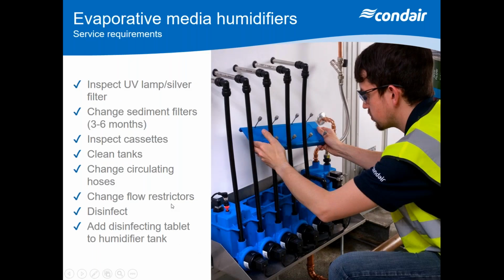So generally from an evaporative media point of view, it's mainly going to be to do with the tanks. You also need to inspect the media. Because it's a glass fibered sheet, it's not particularly robust, so you can't go in there with screwdrivers and poking scale out. You've got to be cleaning it with a very, very light brush on the face of the media.